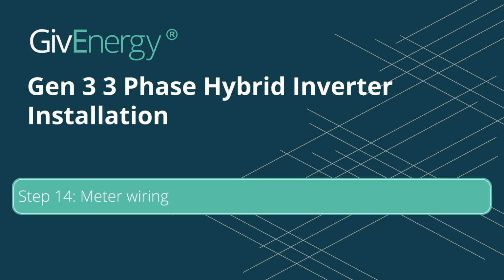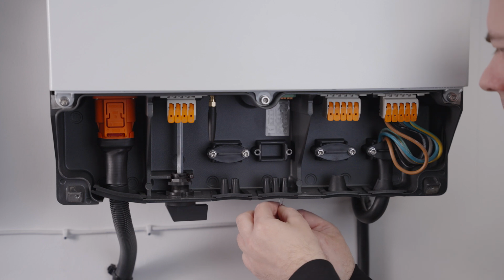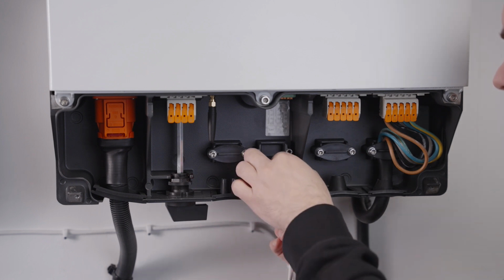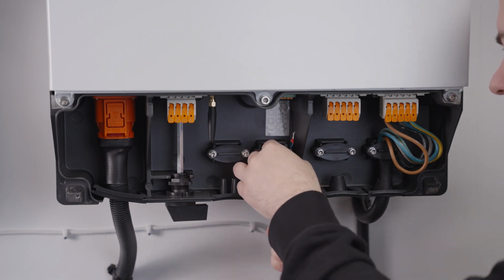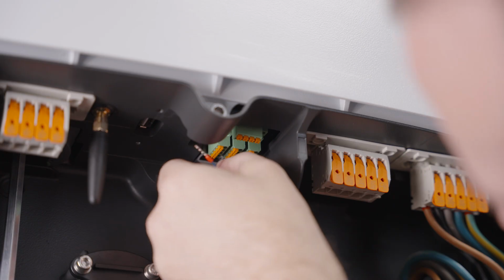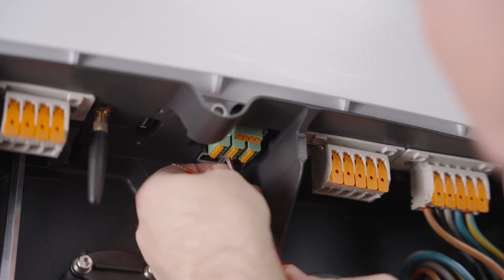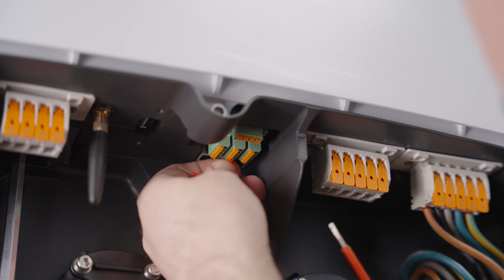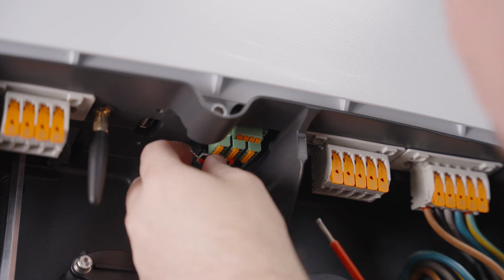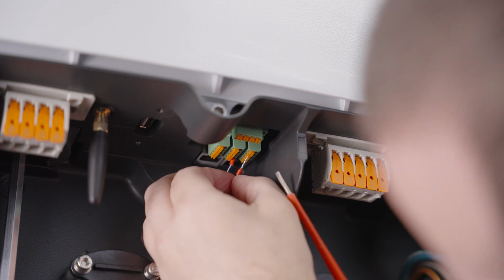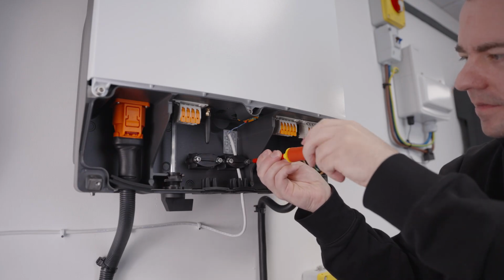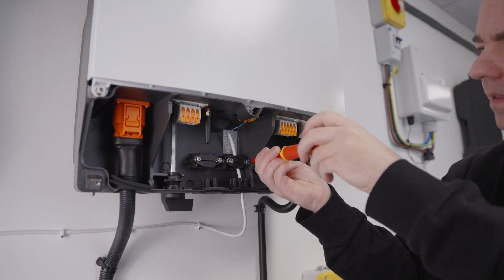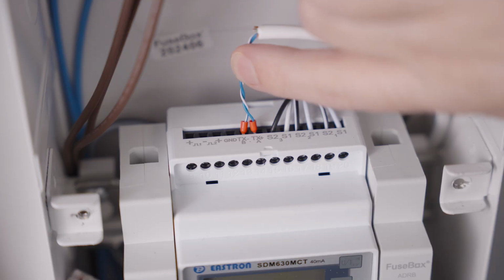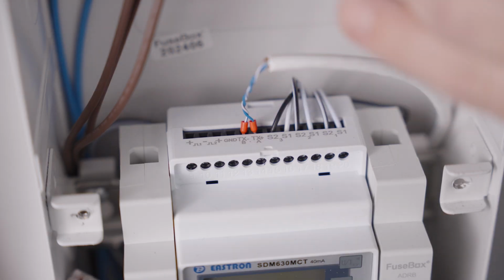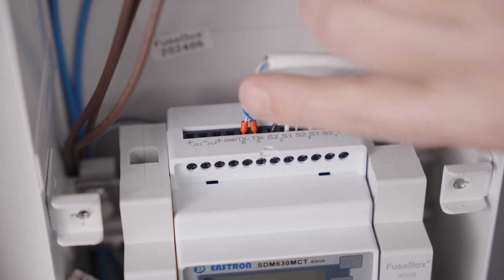Step 14. Meter wiring. Strip the meter comms cable to the required length. Now pull the meter comms cable through the grommet. Install the meter comms cable into a push-fit green connector. Be careful not to damage the cable cores. When using Cat5 solid core cable, if it is overbent, it may break. This creates unstable and intermittent readings. Ensure you have correct polarity. The polarity on the inverter must match the polarity on the meter.